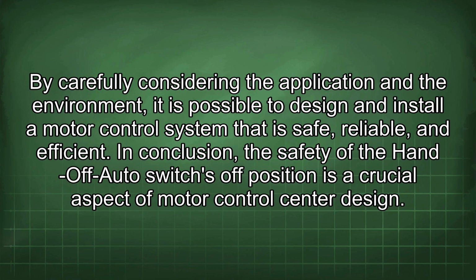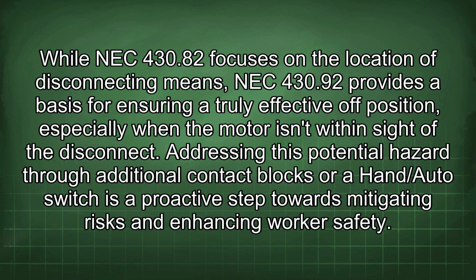In conclusion, the safety of the hand-off auto switch's off position is a crucial aspect of motor control center design. While NEC 430.82 focuses on the location of disconnecting means, NEC 430.92 provides a basis for ensuring a truly effective off position, especially when the motor isn't within sight of the disconnect.